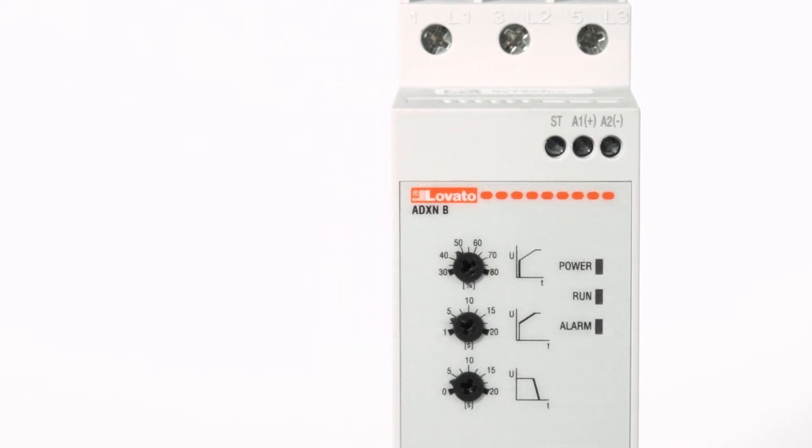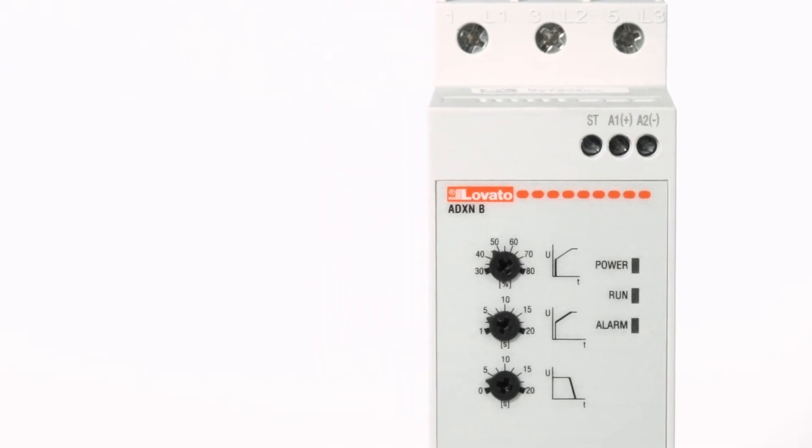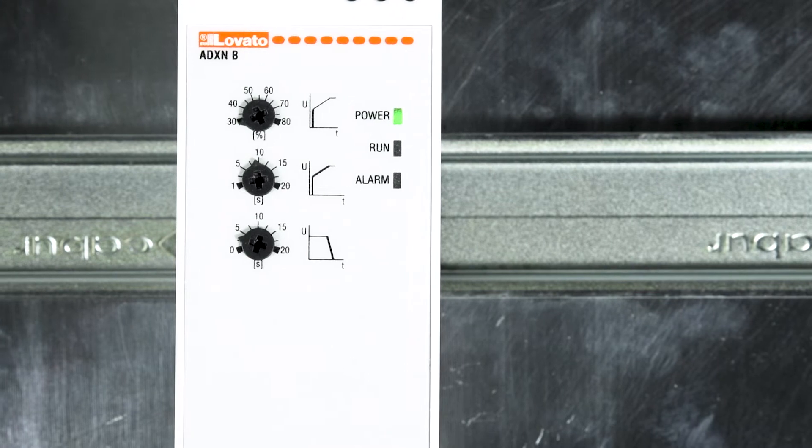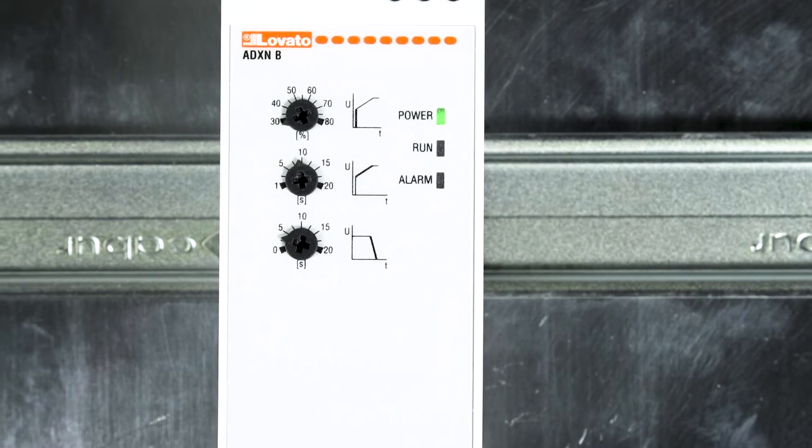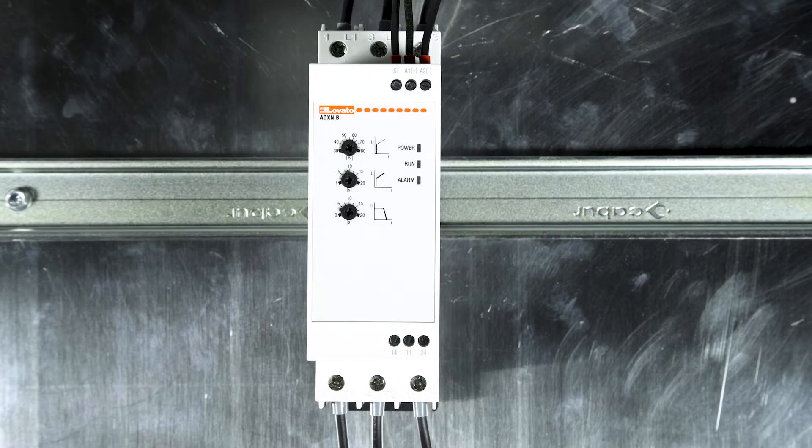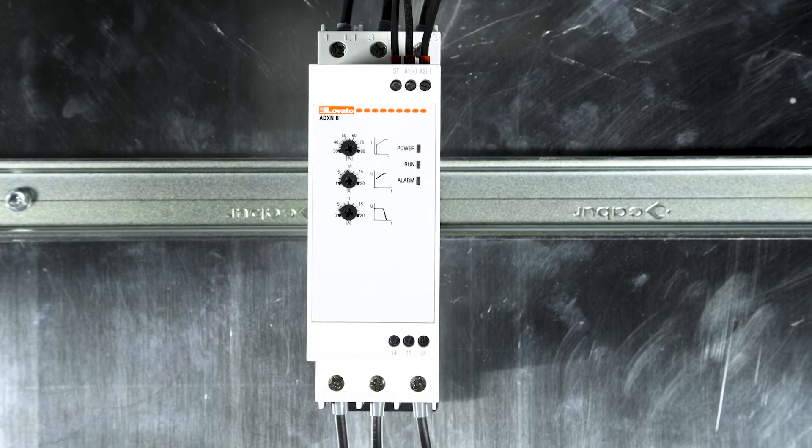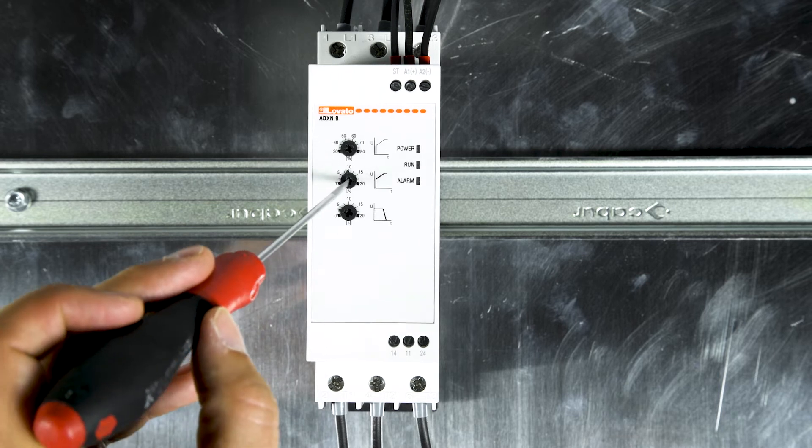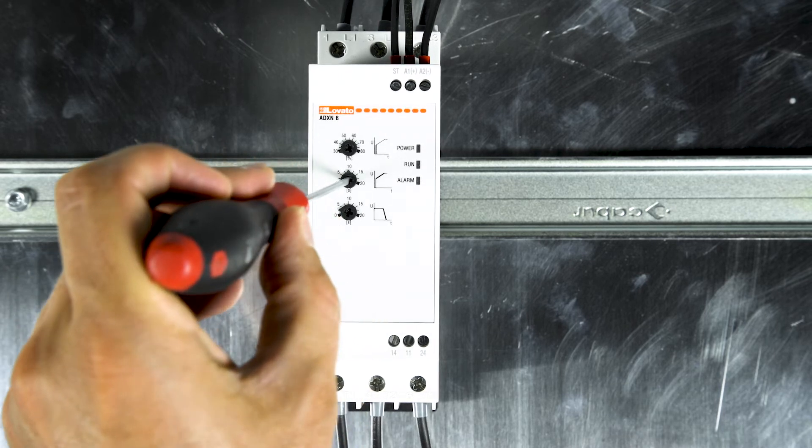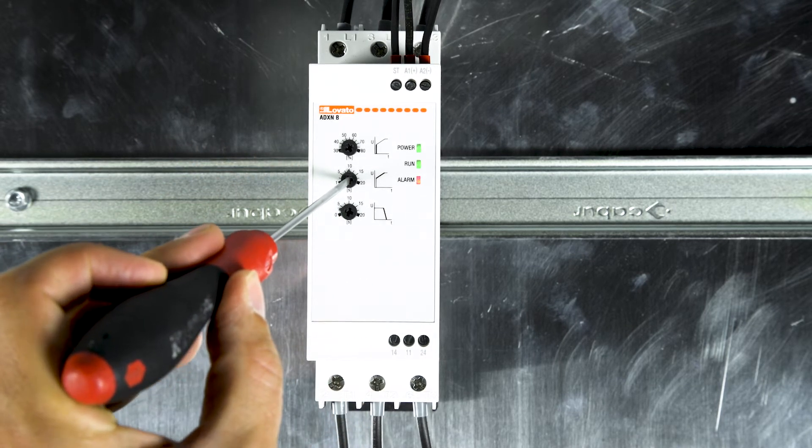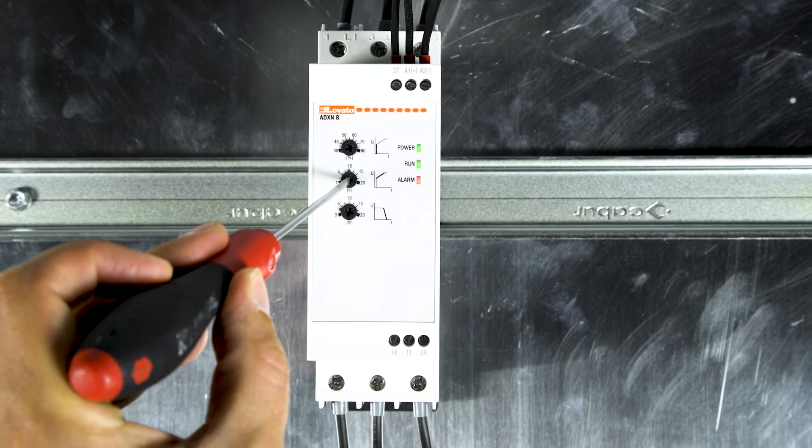To enable the phase sequence control when the soft starter is powered up, at the end of the flashing of the front LEDs, quickly turn the central potentiometer first to the maximum and then to the minimum value for two consecutive times in this way.